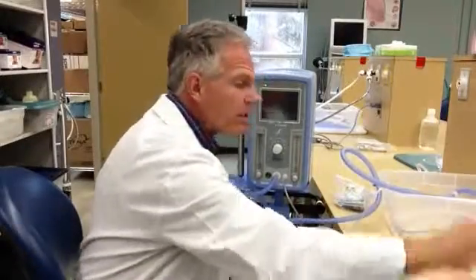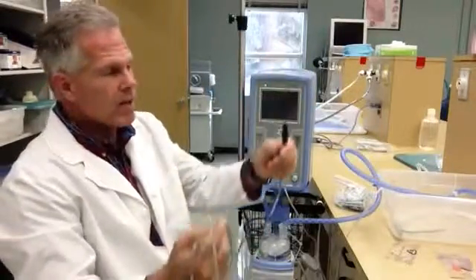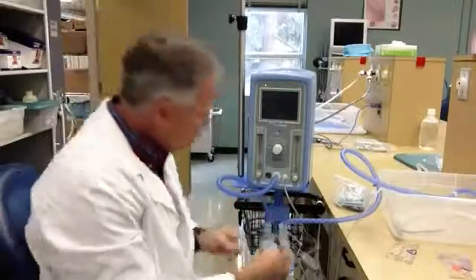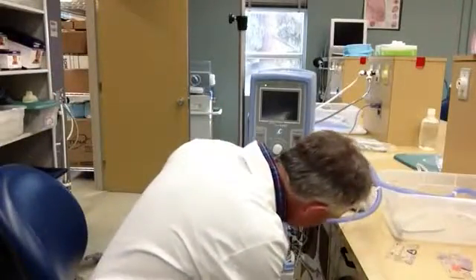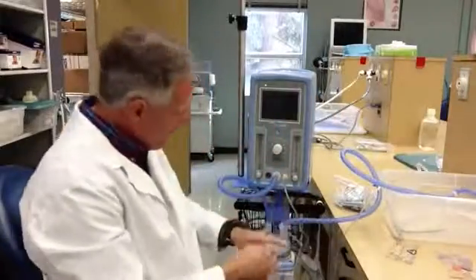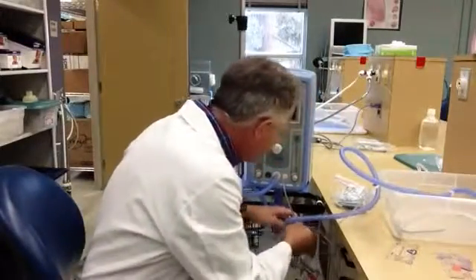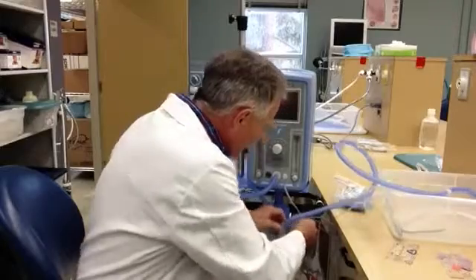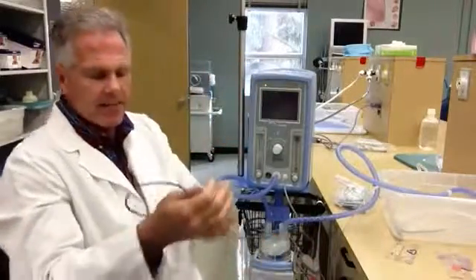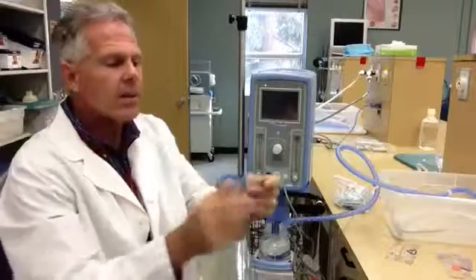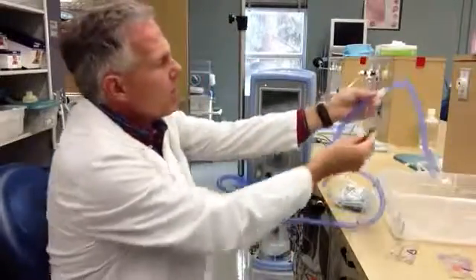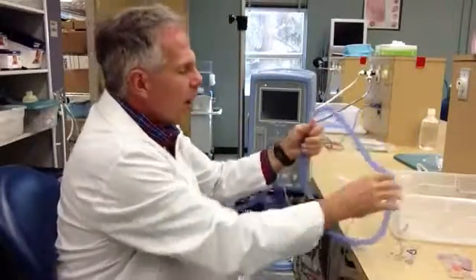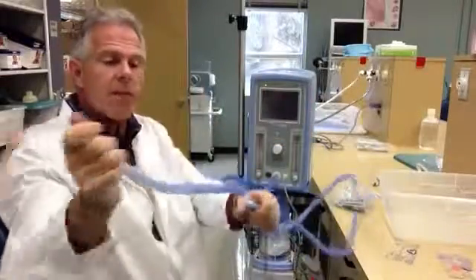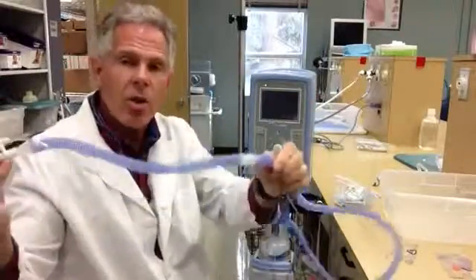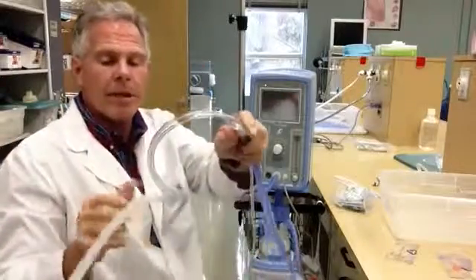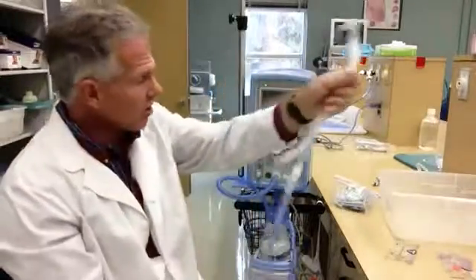Next, we need our temperature probes. If we're going to deliver heated humidity, we want to make sure it's at the right temperature. Okay, so we've got a heated probe here, just fitting in. Make sure that's nice and tight in there. And our last temperature probe goes close to the patient's circuit, right close to the patient, but outside the isolette, because the heat from the isolette might inadvertently shut off our heated humidity. All right? So that's the basic circuit all set up here.